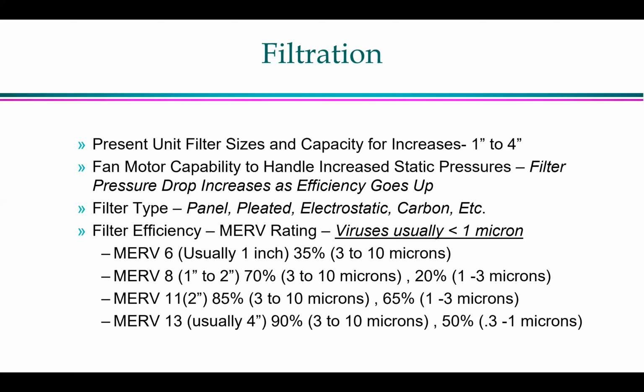But these are the ranges down here: MERV 6, 8, 11, 13. MERV 13 is what LEED and some of the other codes or standards are starting to require. You can see that the MERV 6, the 1-inch 35% filter, handles the big particles, 3 to 10 microns. The MERV 8 gets better. It'll start down to the 1 micron. MERV 11 doesn't have a real big pressure drop as opposed to the 13. But by the time you get to the MERV 13, and you can get 2-inch MERV 13 filters, the particles go down as far as what you can catch. So next.